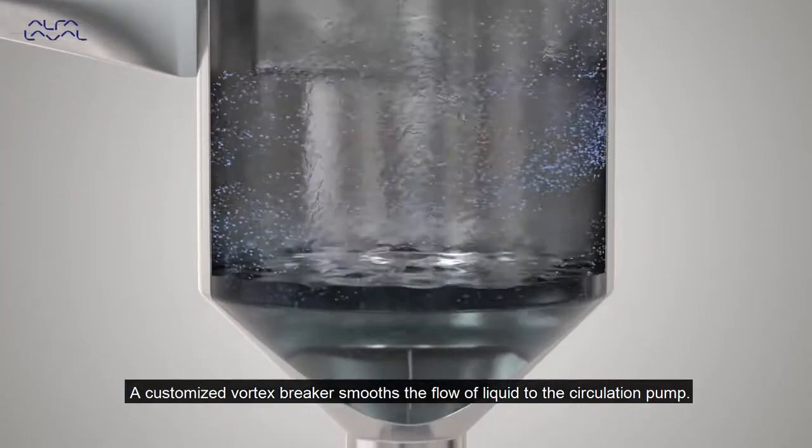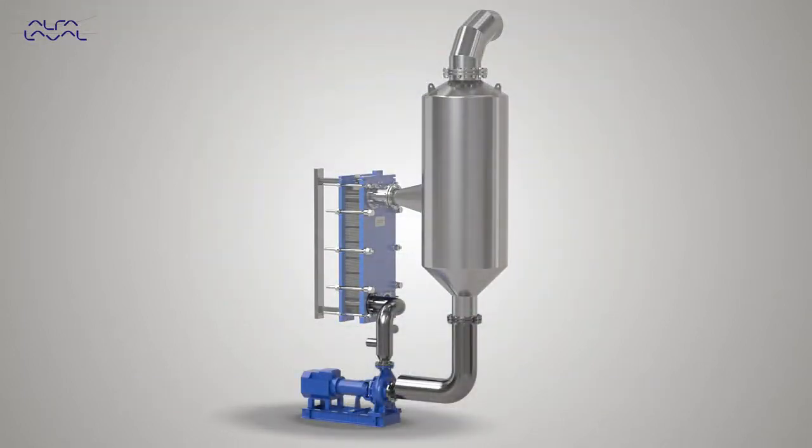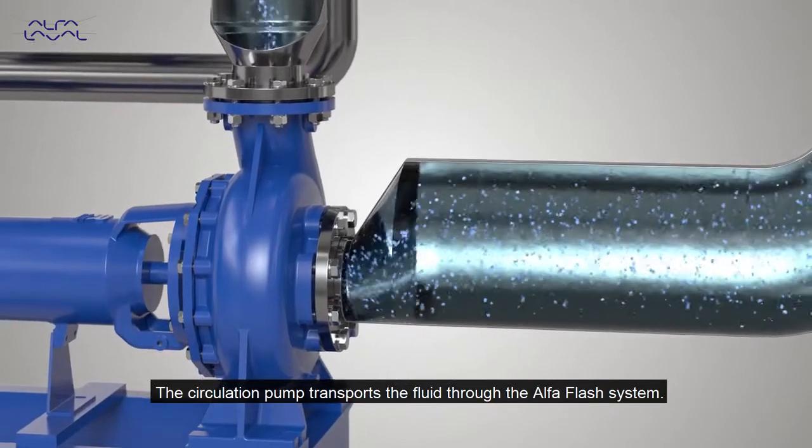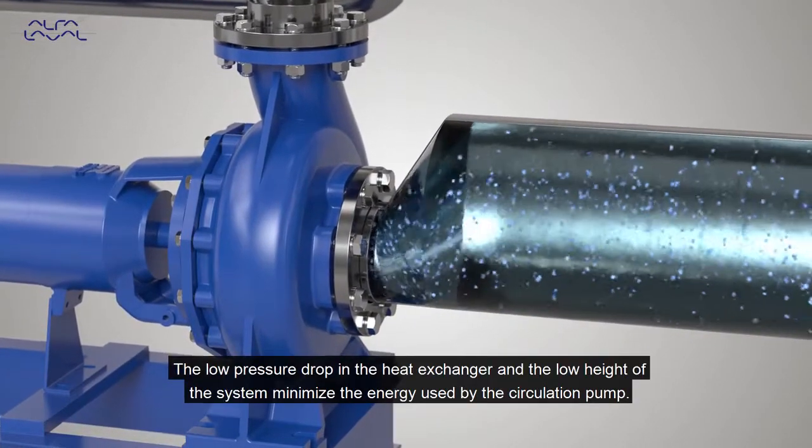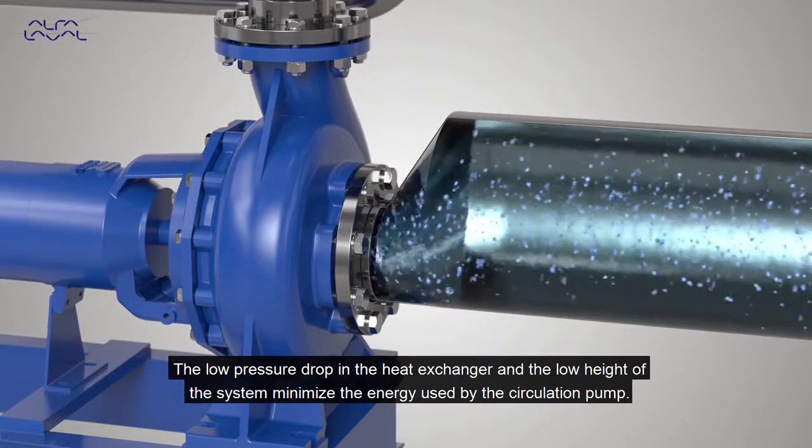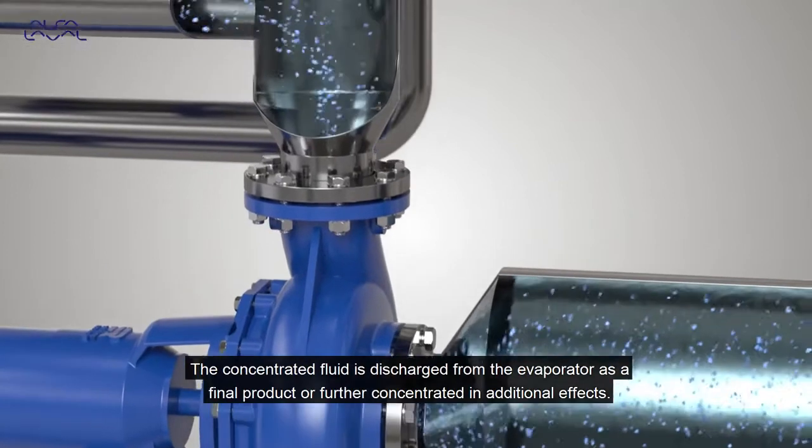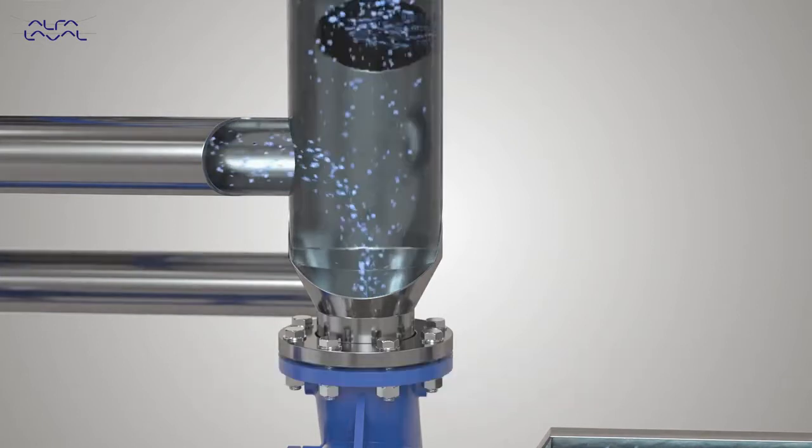A customized vortex breaker smooths the flow of liquid to the circulation pump. The circulation pump transports the fluid through the Alfa Flash system. The low pressure drop in the heat exchanger and the low height of the system minimize the energy used by the circulation pump. The concentrated fluid is discharged from the evaporator as a final product or further concentrated in additional effects.